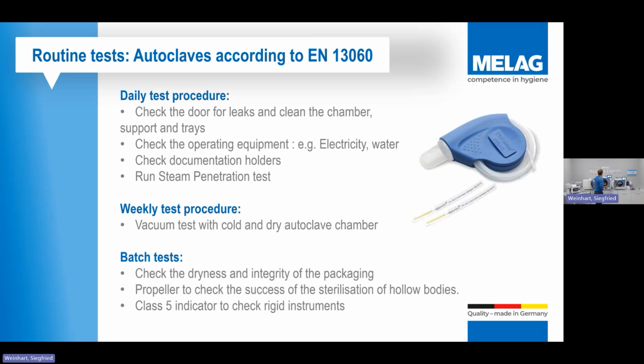We then got routine tests that we have to do with them. All of these are driven by the manufacturers, very much down to what the manufacturers will recommend. But typically what we're doing on a daily basis for an autoclave is we're making sure that the door gasket is in good condition, that we've got no rips or tears in these door gaskets, okay? And that also the door opens and closes correctly, that there's no grinding.